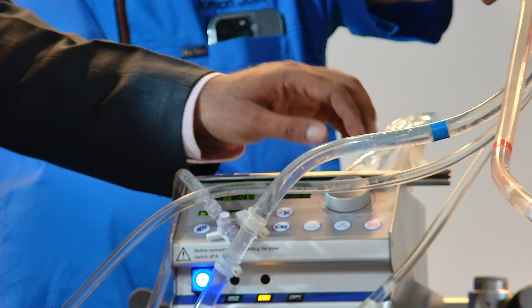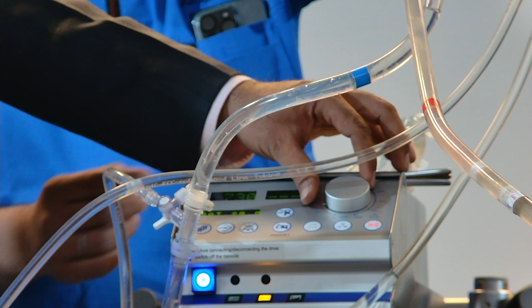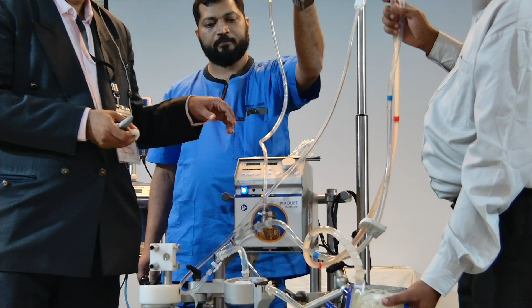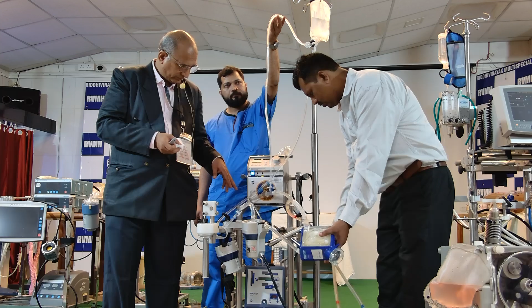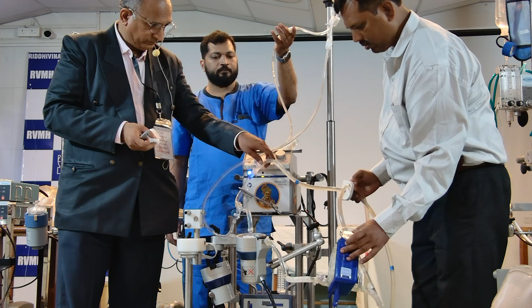Now when you are priming the circuit, you have to prime the circuit in two stages. One is the priming with the crystalloid, that is just to de-air. And suppose the patient's hemoglobin is low or you want to add something else, additives, then first is crystalloid priming followed by additive priming. So priming can be done in two stages. Okay. Now the basic principle of priming, always remember, is that air moves up. Okay. So that is the basic principle.